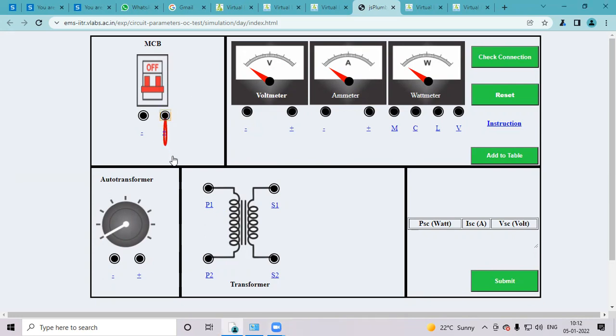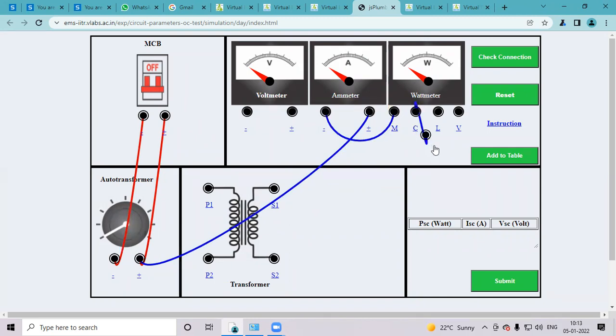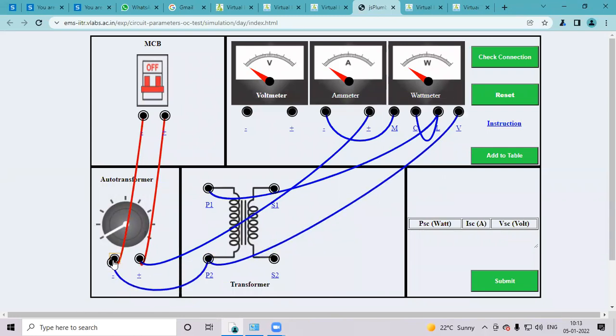Positive terminal of the supply is connected to positive terminal of the dimmer, negative terminal of the supply to negative terminal of the dimmer. Remaining connection is same, only the secondary connection is different. On the secondary side where we had connected the voltmeter, now we will directly short circuit it. C positive terminal is connected to positive terminal of the ammeter, next terminal of the ammeter connected to M. C terminal and L terminal are common, L terminal connected to P1, V terminal connected to P2. That means the primary winding's second terminal is directly connected to negative.